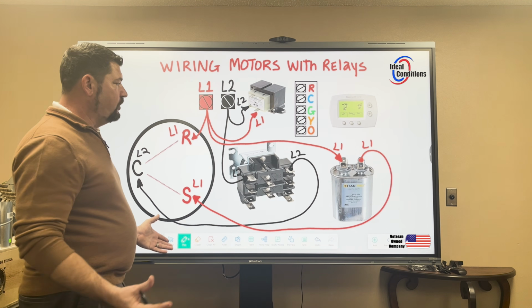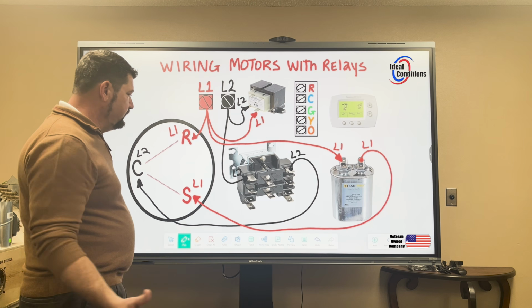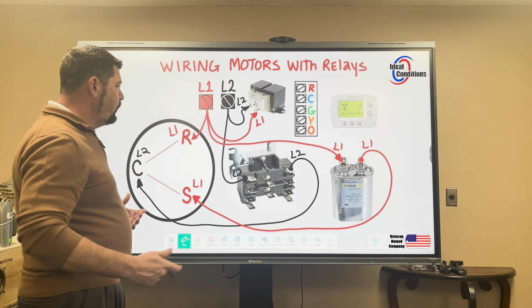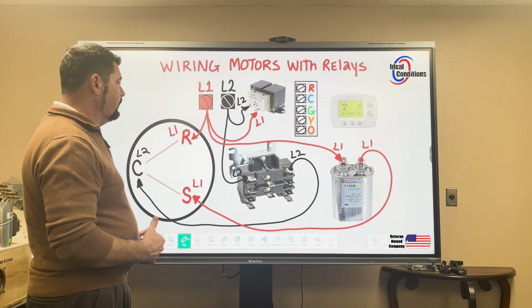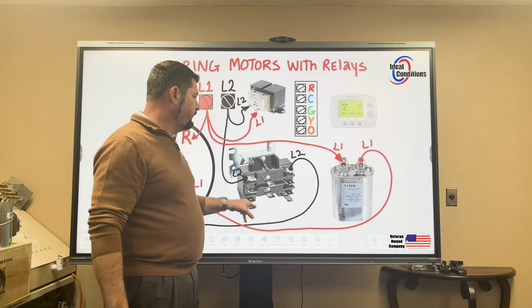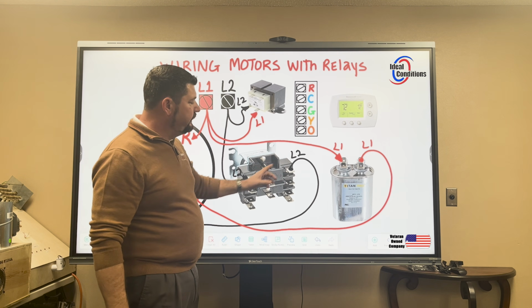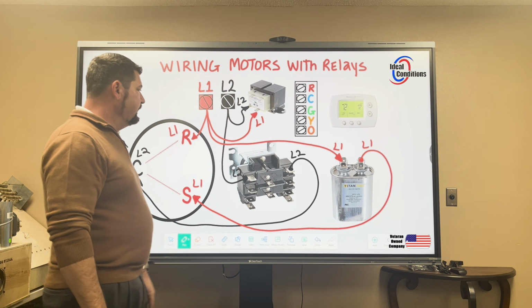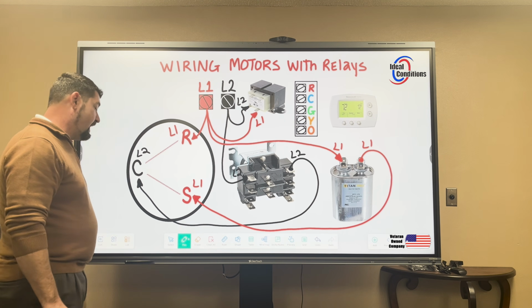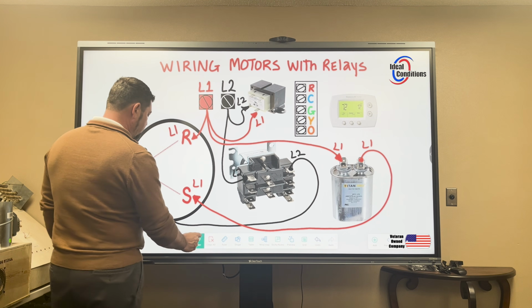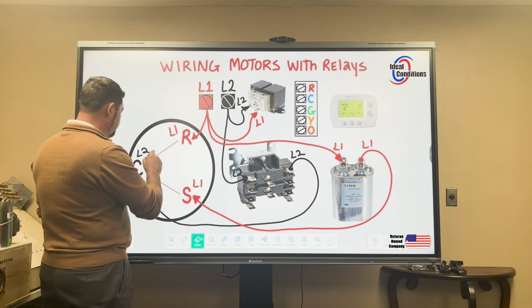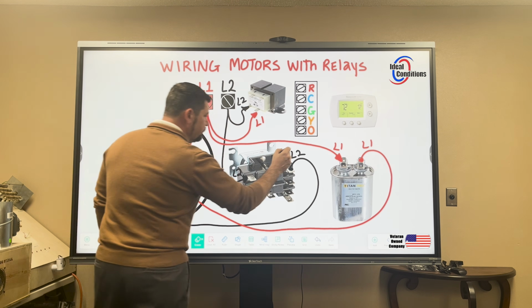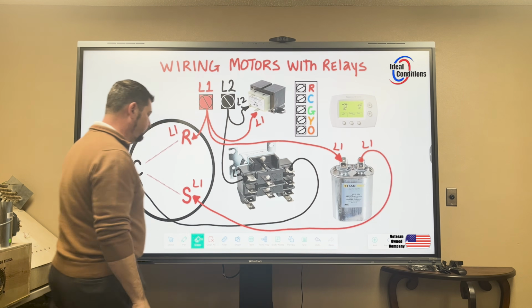Now, one of the things I've showed you on the other videos, I'm going to continue to keep in mind: where is power present right now? Because this relay does not have 24 volts on it. So am I really reading L2 here? And the answer is no. I'm not reading L2 there. So I'm going to back a few of these back down to no value so we can see what value is really there.